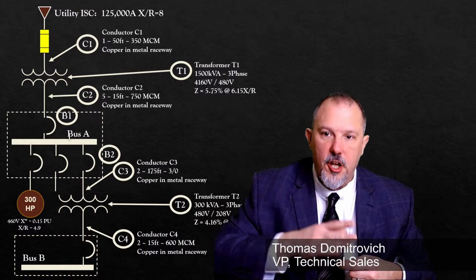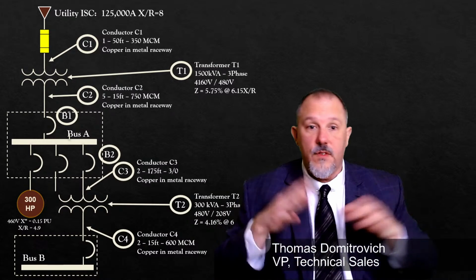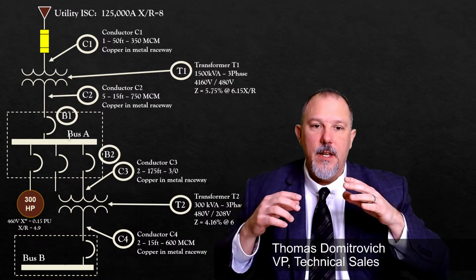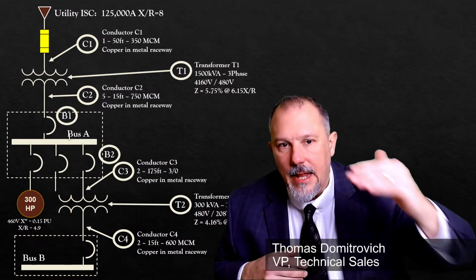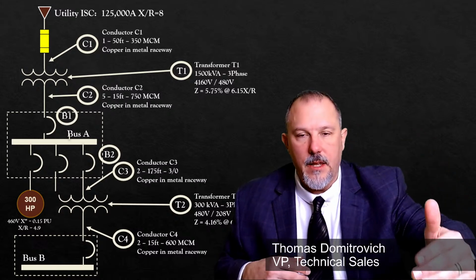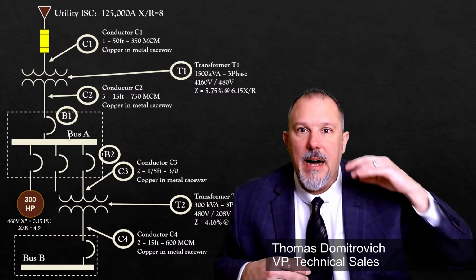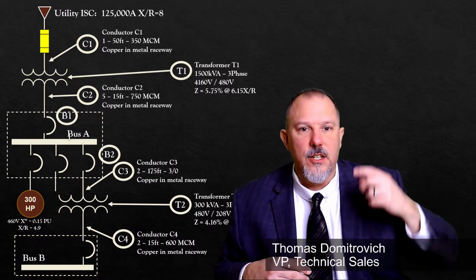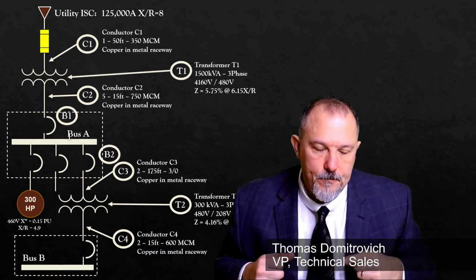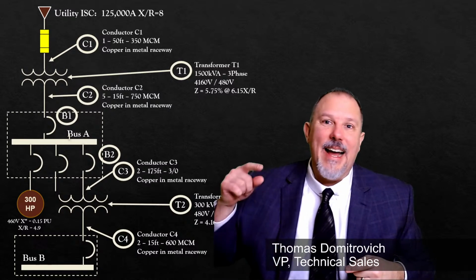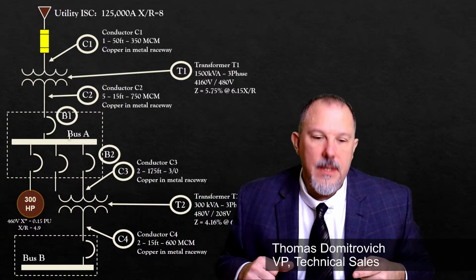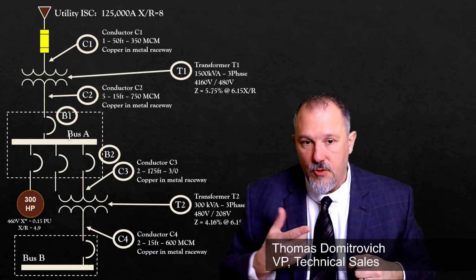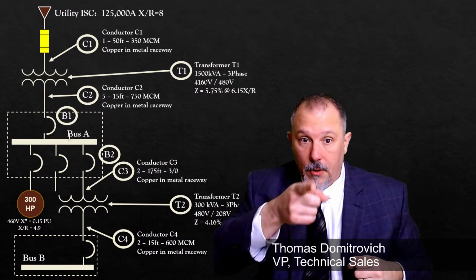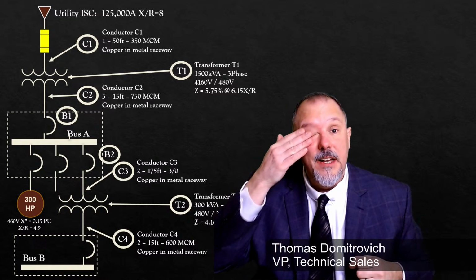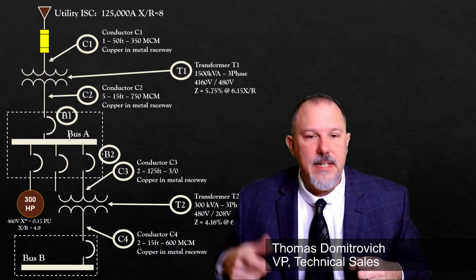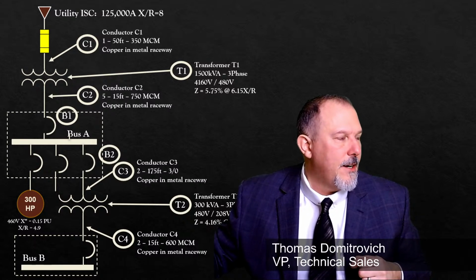Now, the argument and the debate that I have seen in this world of selective coordination is, if I put an intentional delay on breaker 1, which is the main in the main panel board, to where my 3-phase bolted fault current is not in the instantaneous region of breaker 1, then I can guarantee you that the incident energy for that downstream transformer is going to, and breaker 2, now breaker 2 might be in the instantaneous region. That's a bad example. Let's say that, remember, we made a change in this one line diagram.